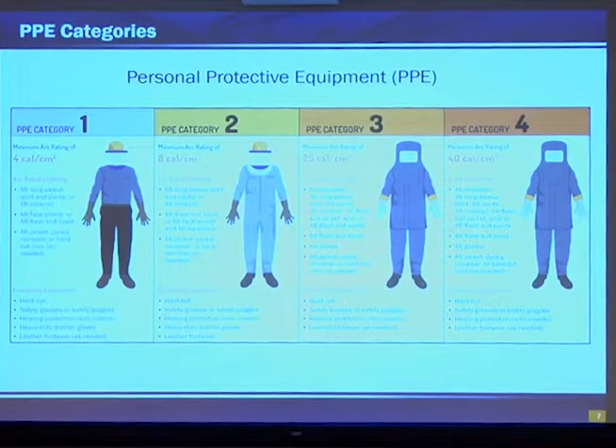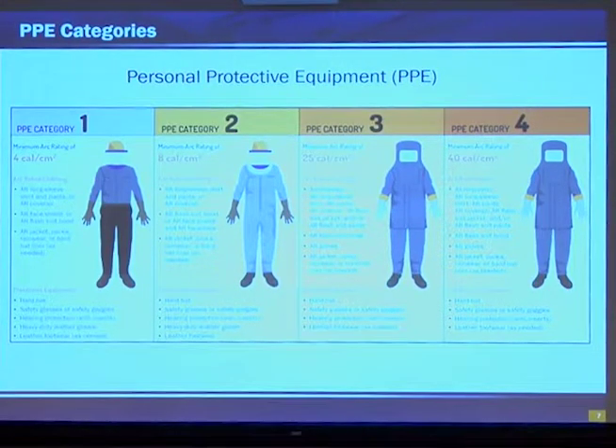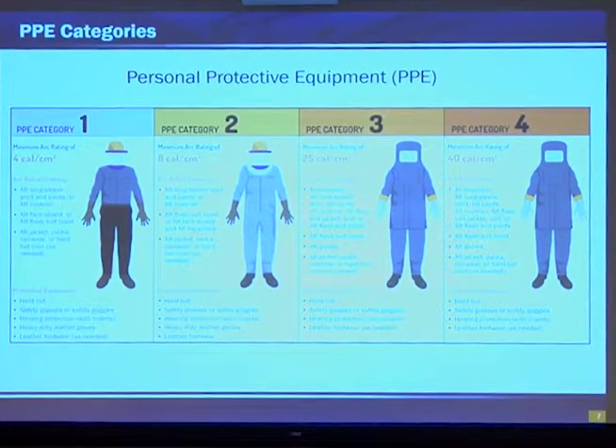Everything else is there. Now, you said everything is the same, correct? So if I have my long sleeve shirt and pants, am I protected? Well, if the incident energy is rated for the category you're in, yes. So if I'm wearing PPE Category 1, I will not be protected for Category 2, but vice versa will be true. So if I have my PPE Category 2 on, I can work in a Category 2 environment and a Category 1 environment. Just want to re-emphasize that.